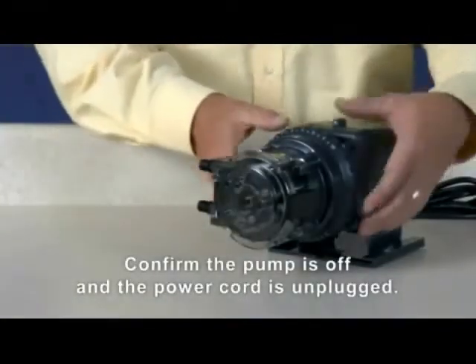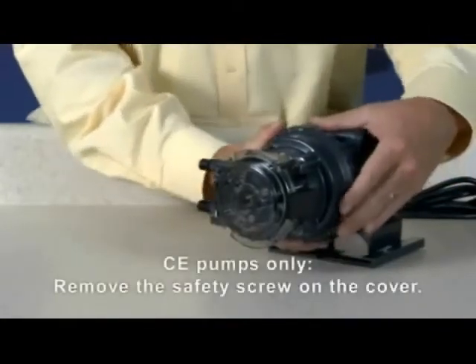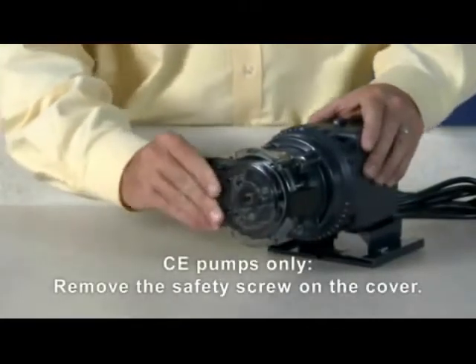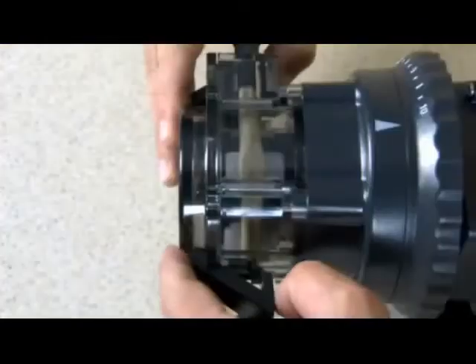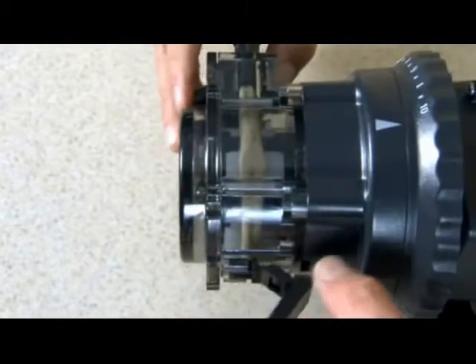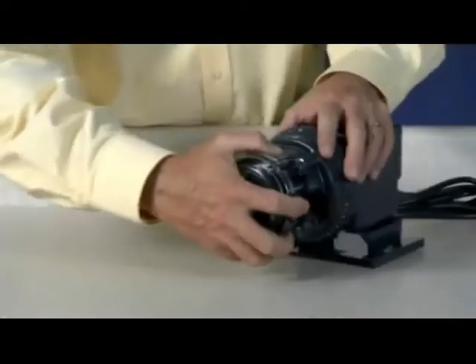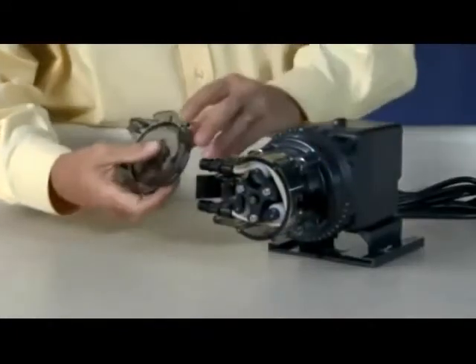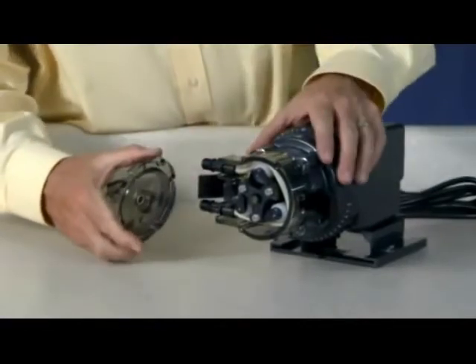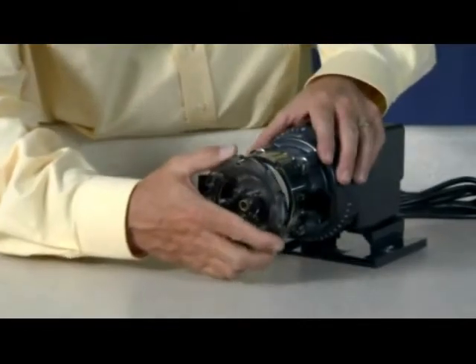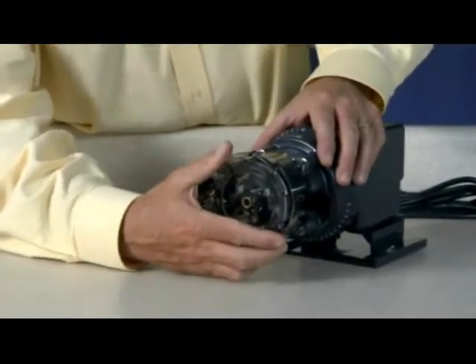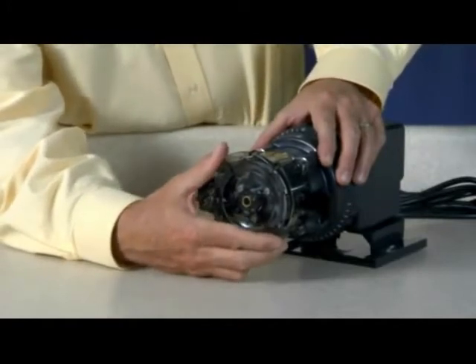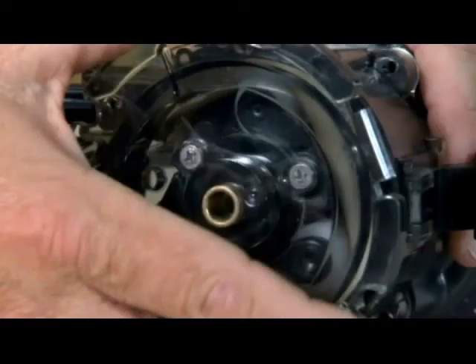Ensure the feed rate control is set to 10. Open the back and front of the latches on both sides of the head. Carefully fold the latches back to prevent contact with the cover. Remove the tube housing cover and flip to use as a tool to collapse the roller assembly. Align the center of the inverted cover with the center of the roller assembly so that the 3 holes on the face of the cover align with the 3 knurled lugs on the roller assembly.